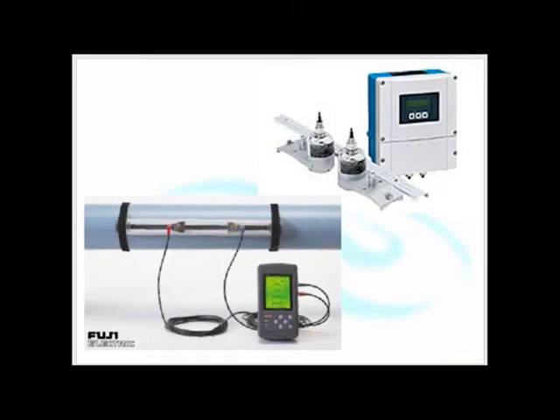Providing the sound pulses can get from the transmitter and the receiver into the fluid, it's going to work. The sort of things that can stop it could be if you have insulation on the outside of the pipe. Well, that's going to stop the sound. A very spongy pipe material, things like old cast iron, will probably stop the sound.